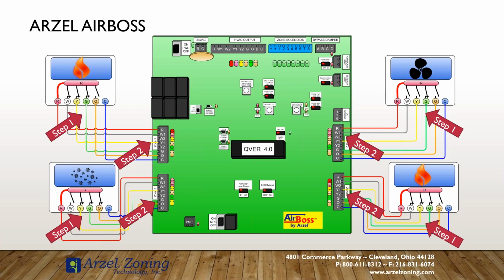And then across the top where the HVAC outputs are, it's red, red, yellow, yellow, green, yellow. That's W1, W2, Y1, Y2, G or green, and reversing valve O, yellow. So we start there. We verify that each thermostat's calling. We verify that the panel's receiving that call, and then we verify our outputs. So we start at the thermostat moving to the equipment, thermostat to zone panel connection. And then from there, we start at the HVAC outputs, and we move to our equipment.